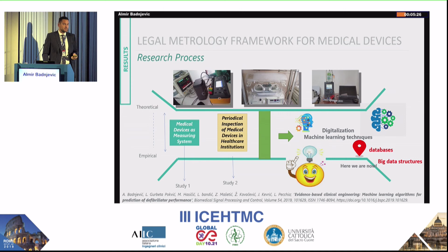Additionally, because we recognized there is no kind of standard, we have evidence-based proof that we need performance standards, etc. We suggested a totally new series of IEEE standards. It's called P2727, and we started with it. It is called, as you can see, Standard for General Vocabulary for Conformity Assessment of Medical Device with the Measuring Function. So that's the whole series, and we already started with the first .1 series, which will be the second standard in that series, which is directly a standard for conformity assessment testing of cardiac defibrillators for legal metrology purposes. And from this point up to 25 different standards, we are already ready with publication of it.